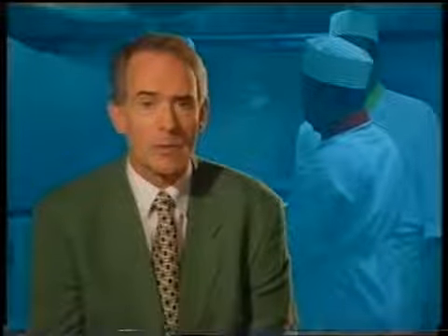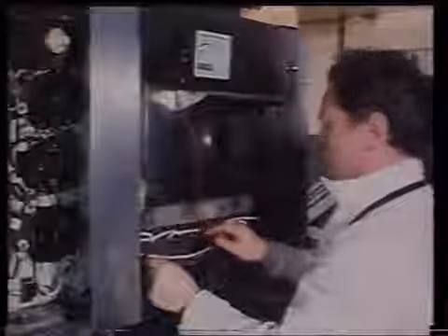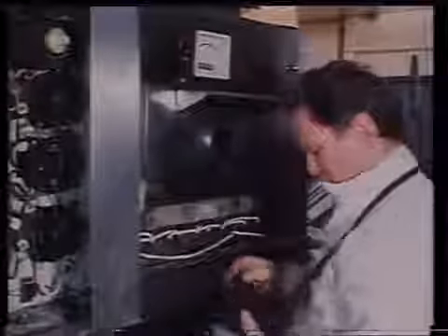Now, some may argue that the wettest and greasiest place on board ship is the galley. Working with electrical equipment there needs extra care for safety. The electrical power in a galley is largely absorbed in producing heat in deep fryers, ovens, hot plates or water heaters. Most other equipment there will utilize small electric motors with their control switches and indicator lamps. Before any maintenance work is done on a unit, isolate the power supply at the galley section board and check the circuit for voltage with a multimeter. Prove it dead.